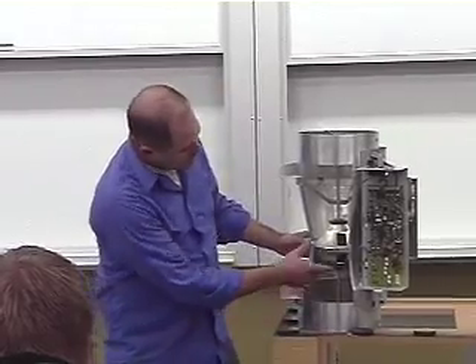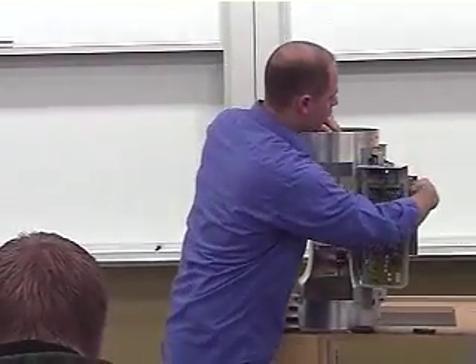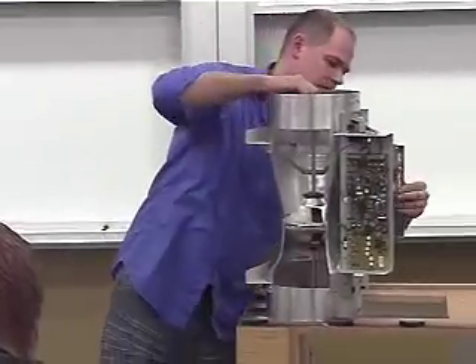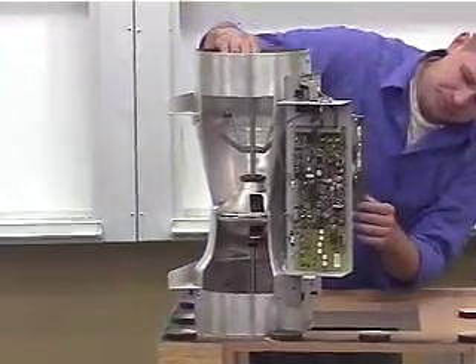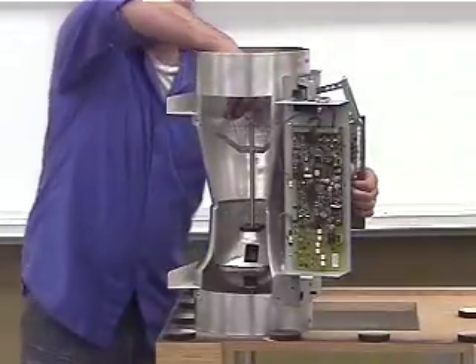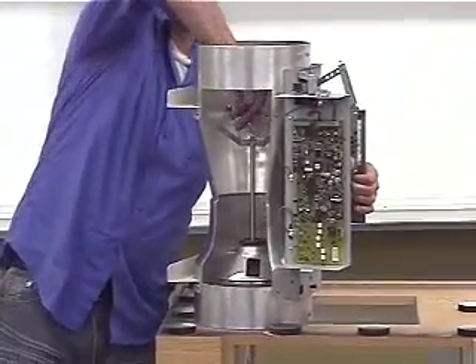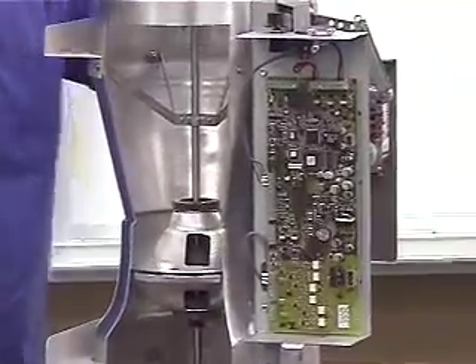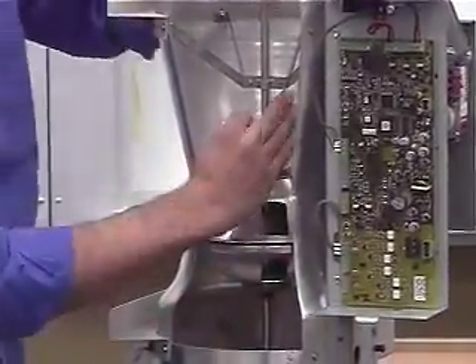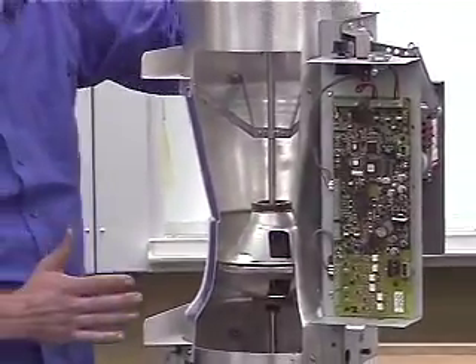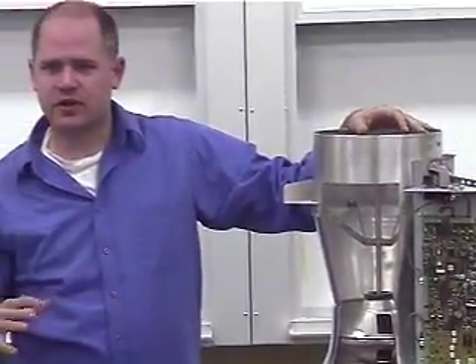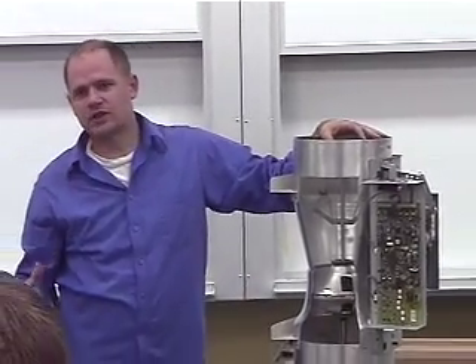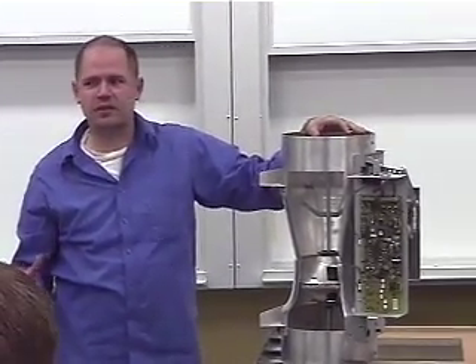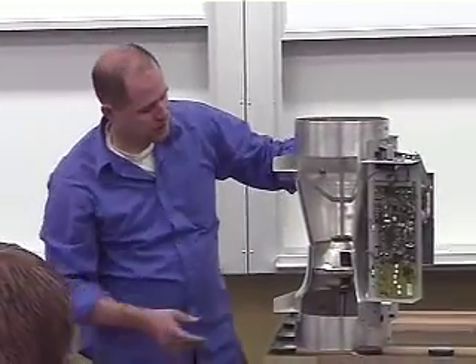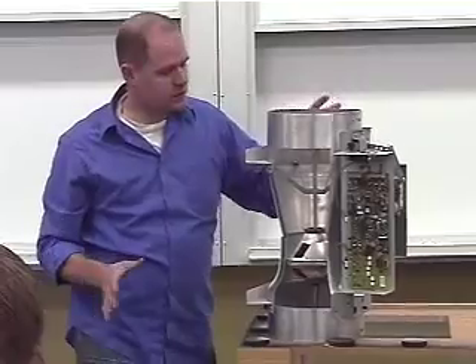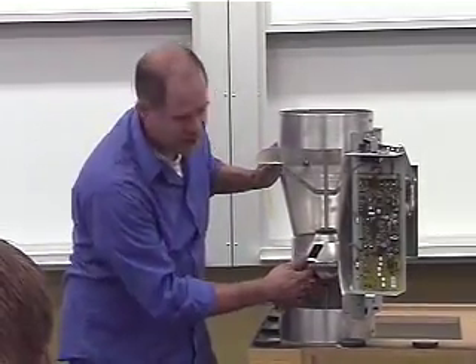This is a Venturi valve design where, as this cone moves in and out, just grab the clutch here and slide it in and out so you can see what's going on. So you can see the cone moving in and out. And as it moves in and out, the air flows around this gap and through the valve. Because of the shape and the design of that, it creates a Venturi effect, which ends up controlling the airflow much more accurately than a regular damper would. And the reason these work is because of this little spring inside here.